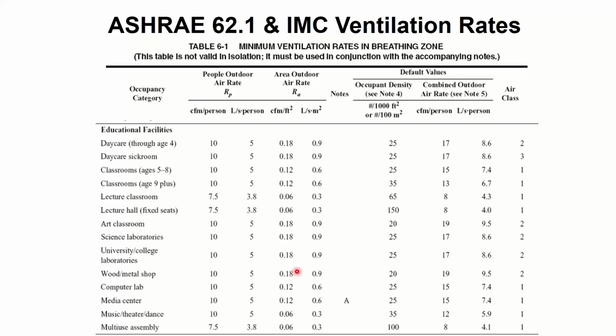Most of the numbers on here you can completely ignore. There are only 2 columns that apply. The first is the CFM per person, and then the CFM per square foot. CFM is cubic feet per minute. So I got a box of air. That's a cubic foot, 1 by 1 by 1. How many of those boxes of outside air can I suck into the building every minute? The other ones, liters per second, ignore those because we don't care about metric right now. We're sticking on US units. So CFM per person and CFM per square foot.